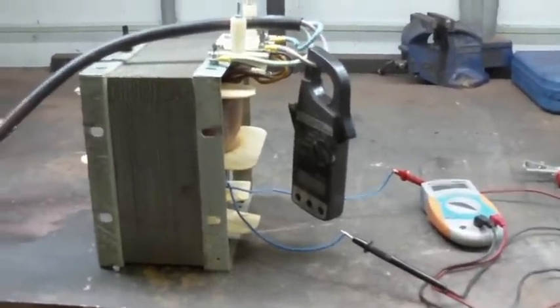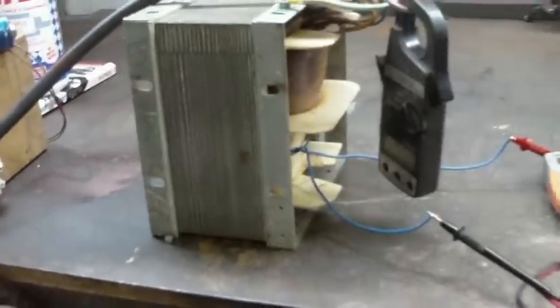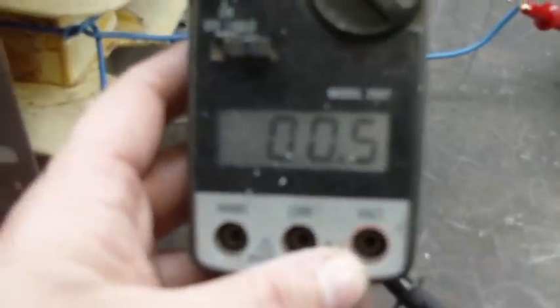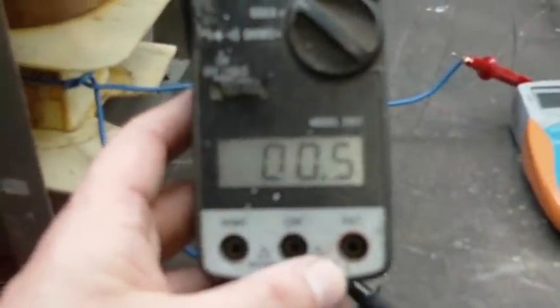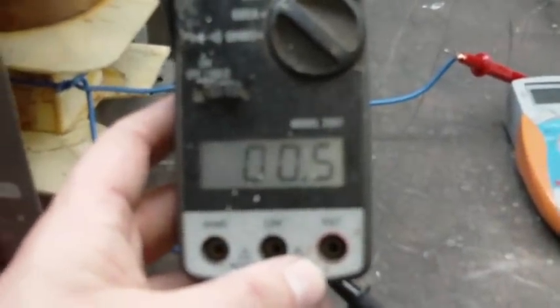Okay, got a bit of progress here. Our transformer is powered up from a 240 volt 32 amp supply, and we've got a clamp meter on the input telling us we're taking about half an amp of magnetizing current at 240 volts.